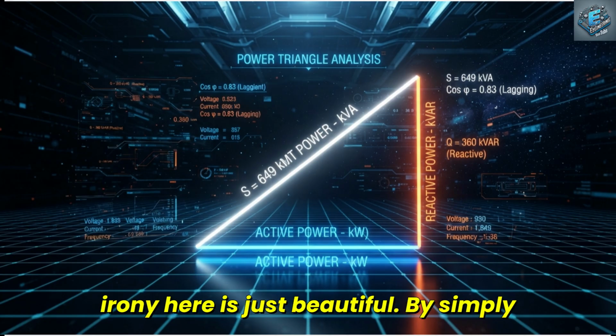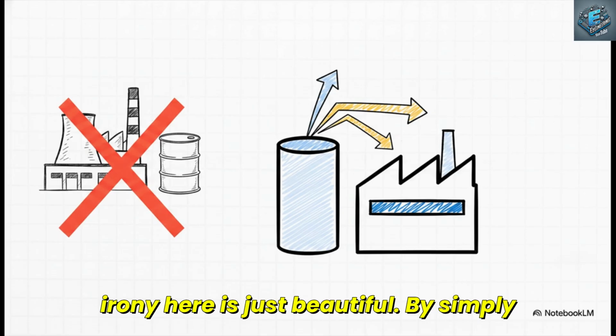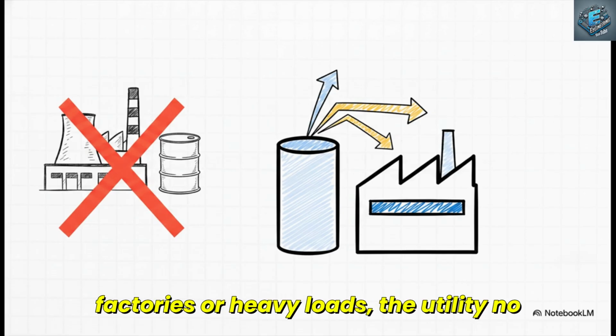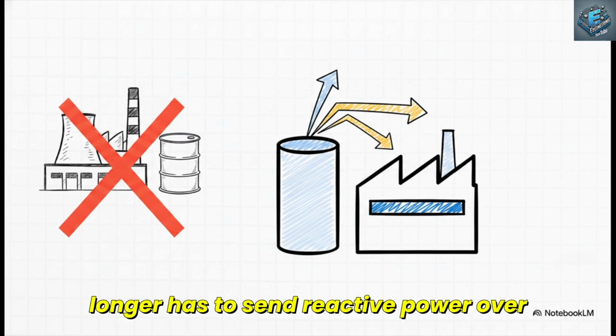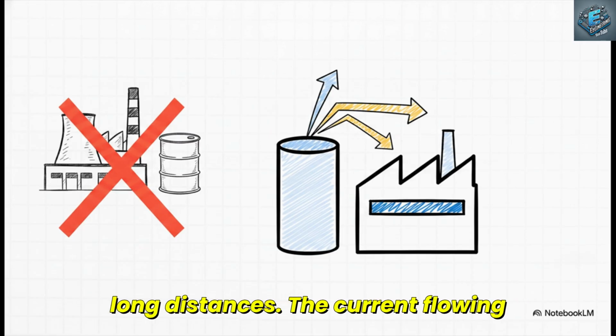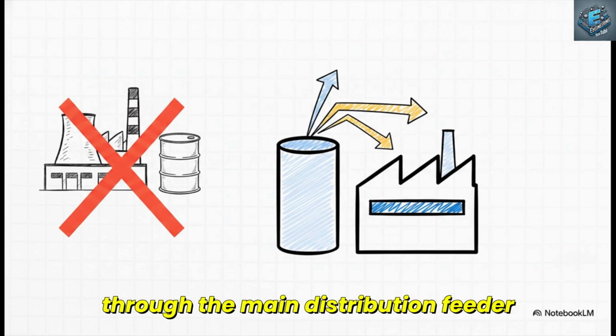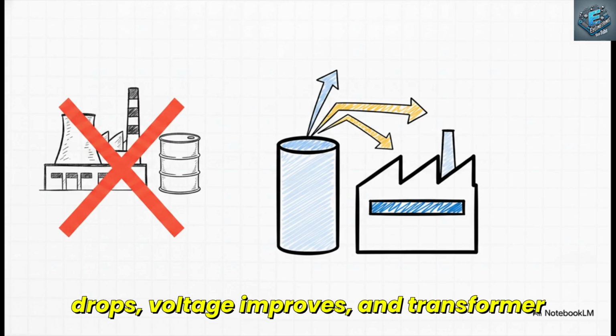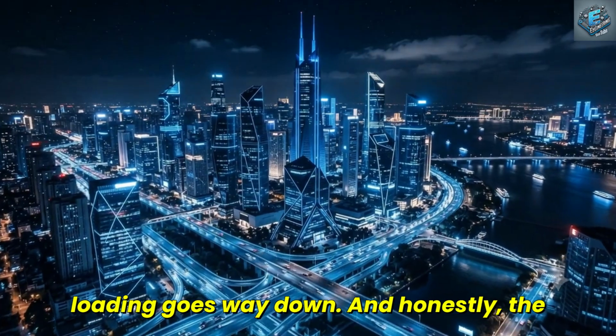The engineering irony here is just beautiful. By simply placing these simple boxes near the factories or heavy loads, the utility no longer has to send reactive power over long distances. The current flowing through the main distribution feeder drops, voltage improves, and transformer loading goes way down.